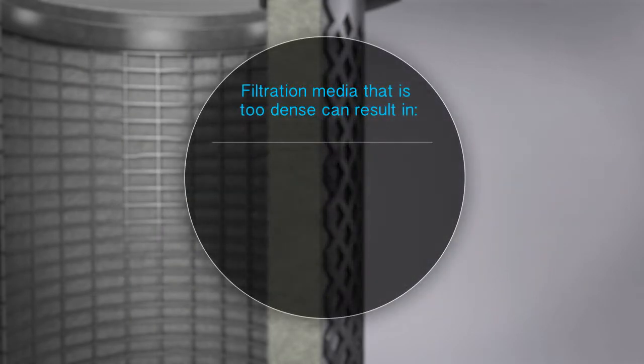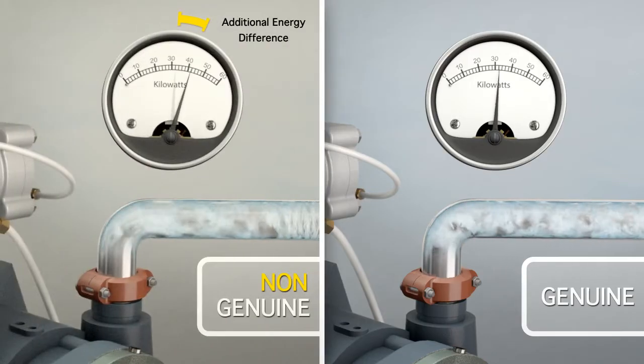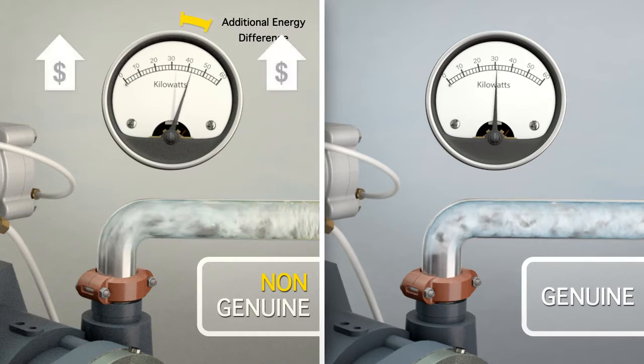The result? Longer on-load times and increased energy costs. It also means your compressor has to work harder to generate the additional pressure needed to compensate for the pressure drop, putting unnecessary load on your motor and further adding to your energy costs.